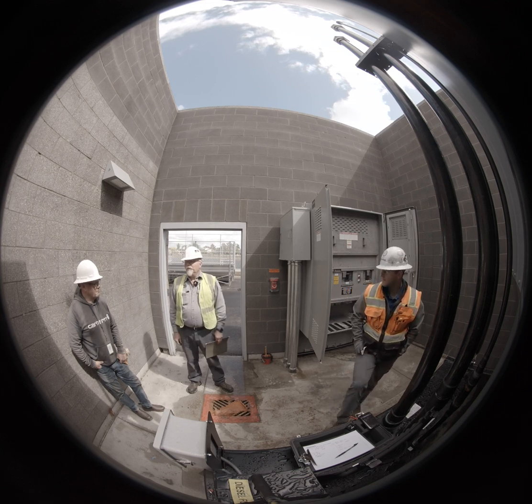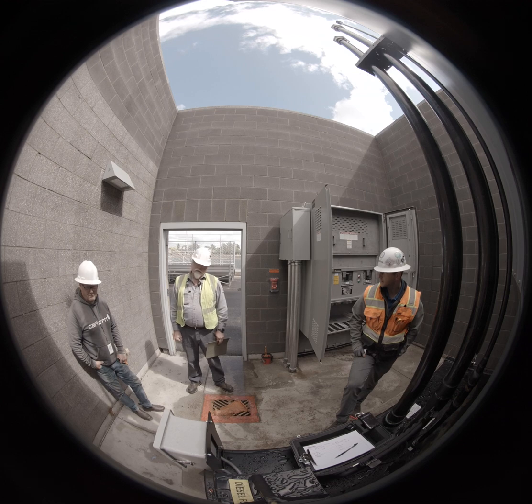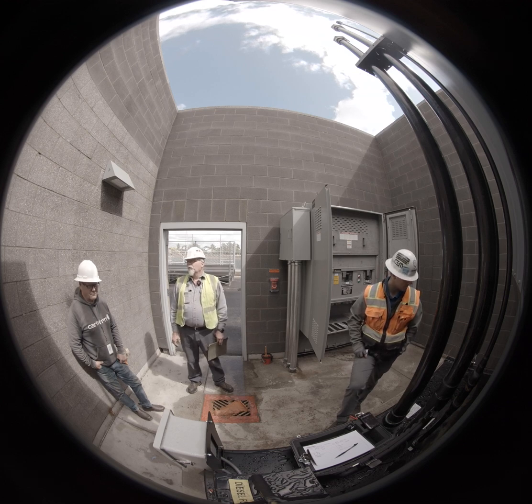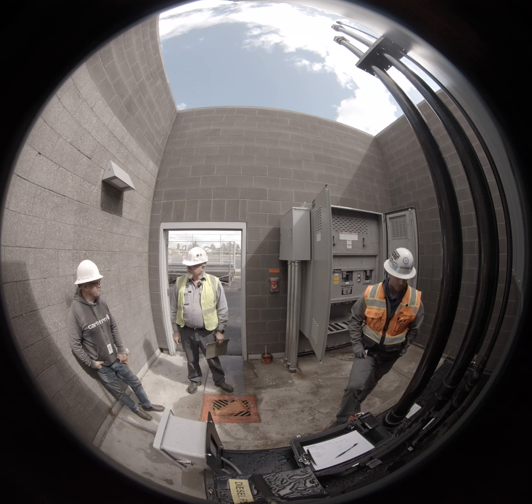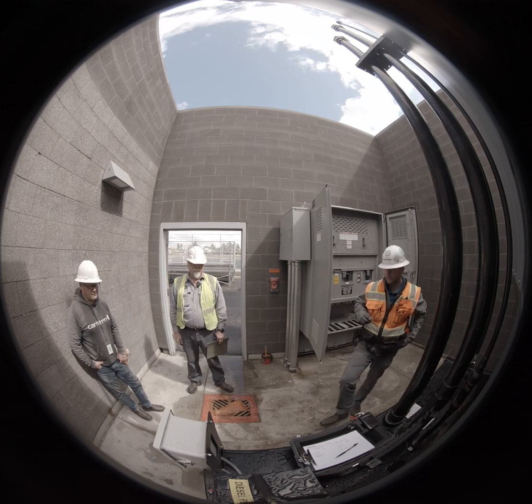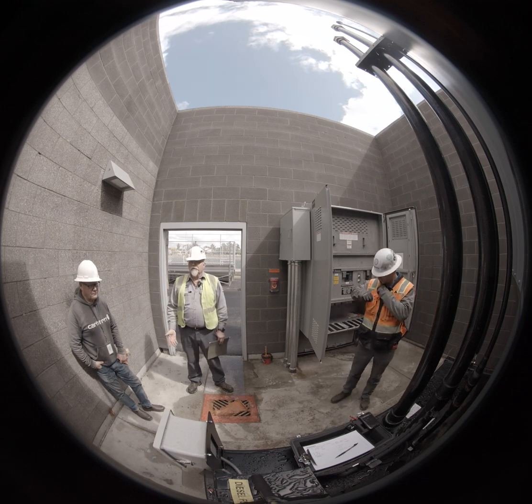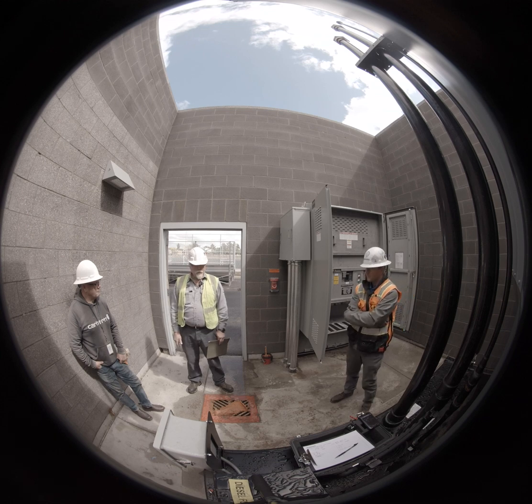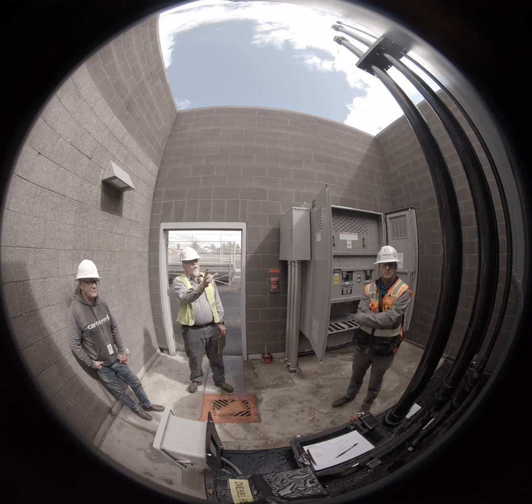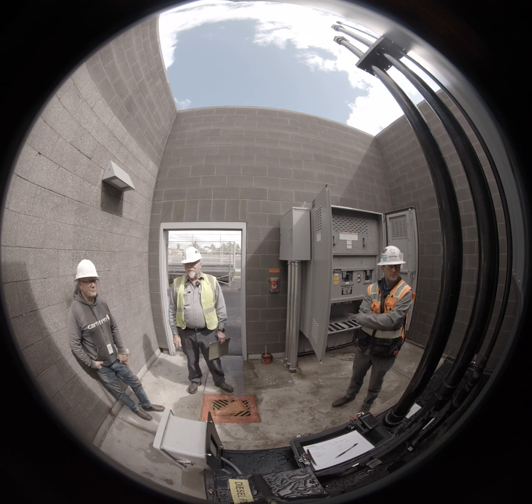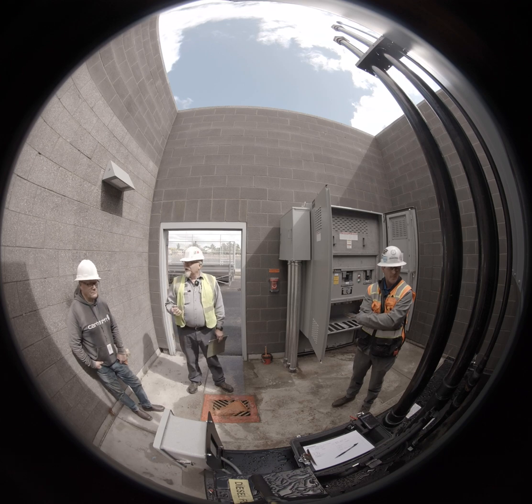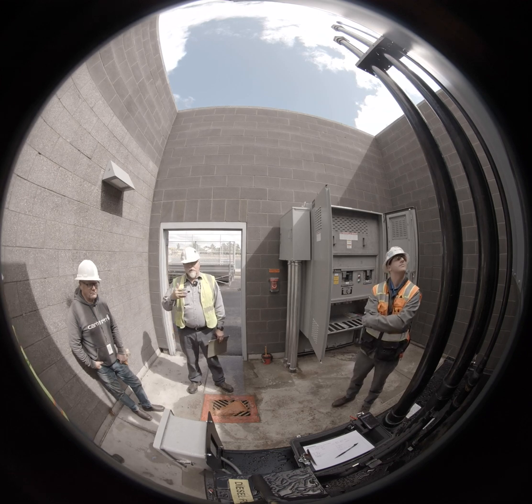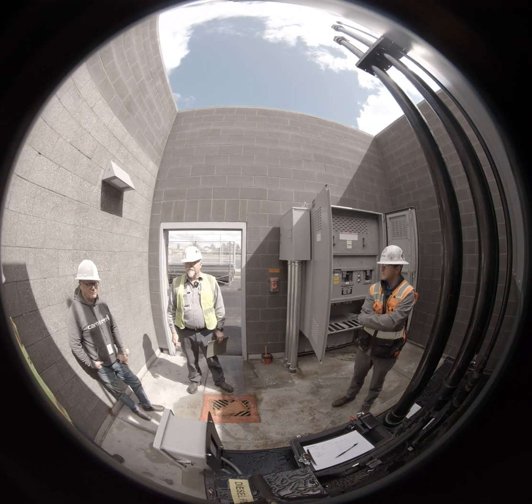Sitting under this machine, we have a double wall sub-base tank that holds the fuel with alarming systems on there for levels as well as containment in the basin. So if we get a leak on this, the alarm panel will go off. So being we're here in the front, I'll give you a couple of guidelines on the fuel tank itself. Over here in front, these pipes are set up so that we have the small one as fresh air makeup to allow the fuel to float up and down. If you don't, you'll draw a vacuum and the engine will starve.